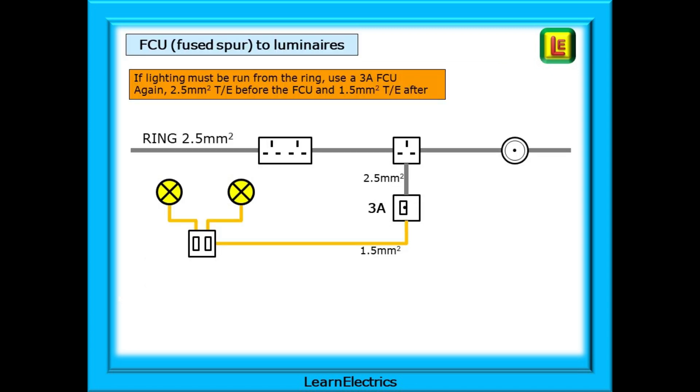If lighting must be run from the ring, use a 3 amp FCU. This will happen where, perhaps, a new conservatory has been added and it is all but impossible to extend the existing lighting into the conservatory. Again, 2.5mm twin and earth before the FCU and 1.5mm after.